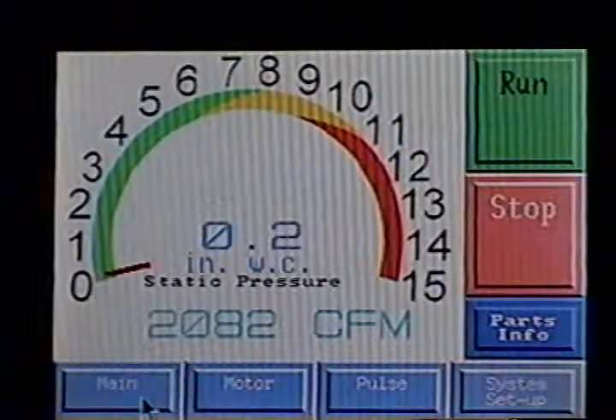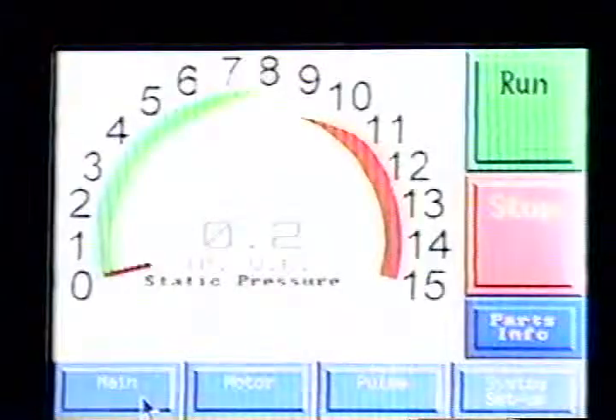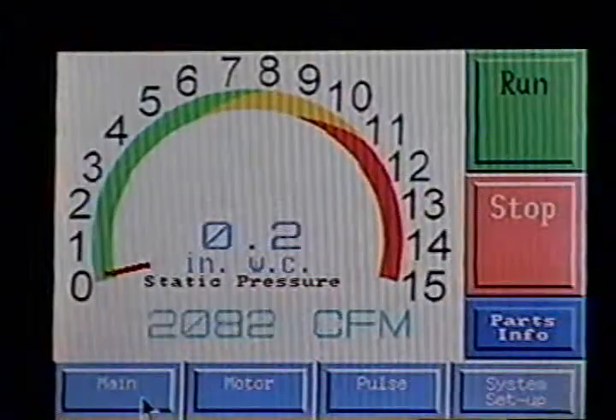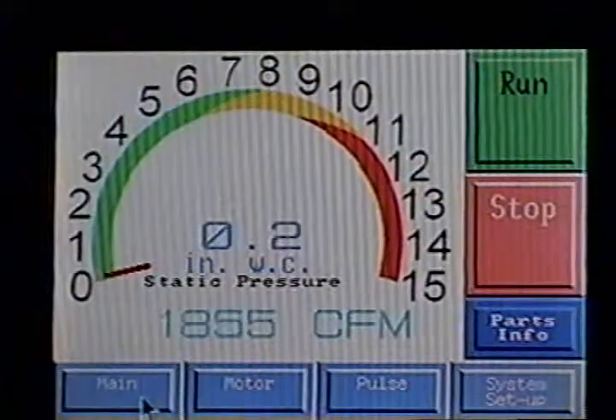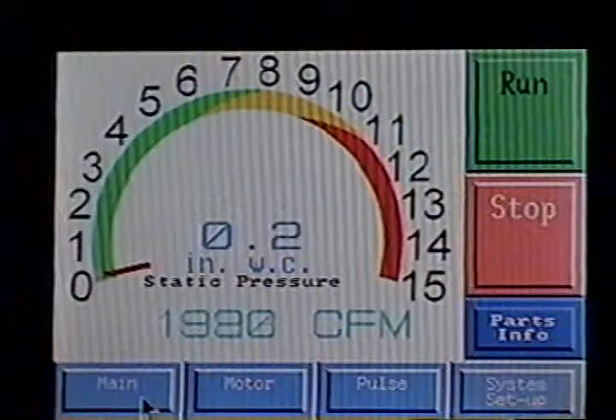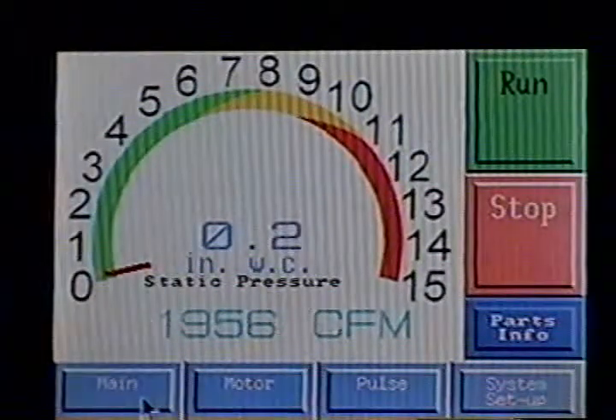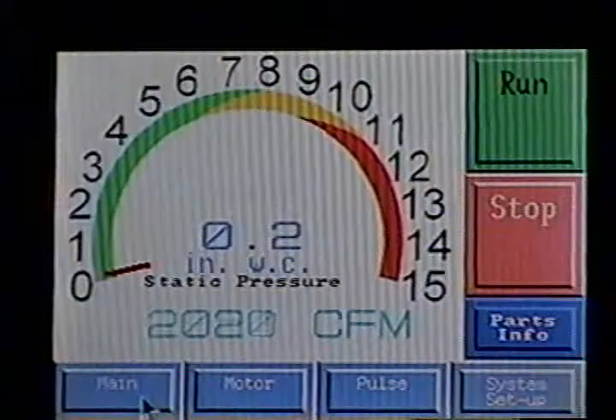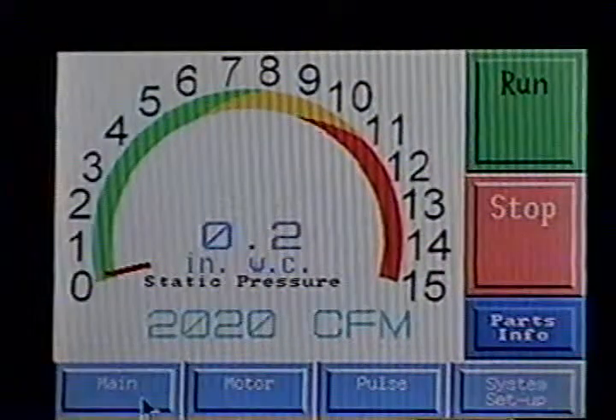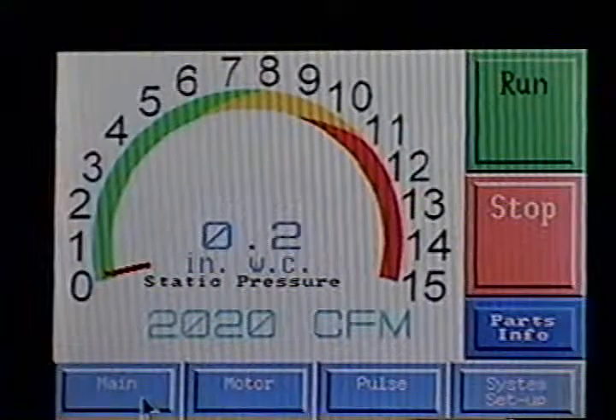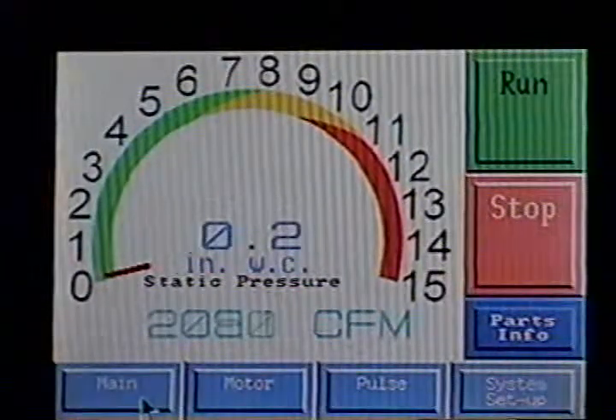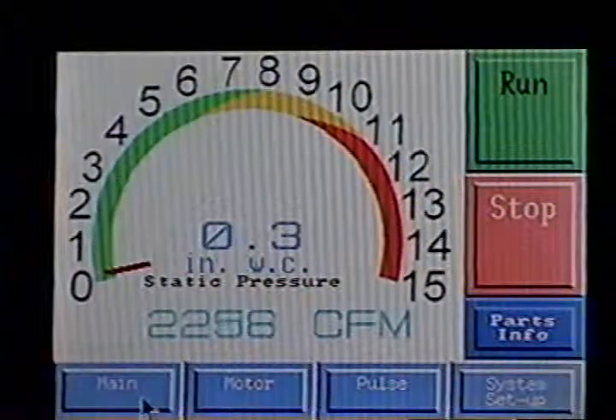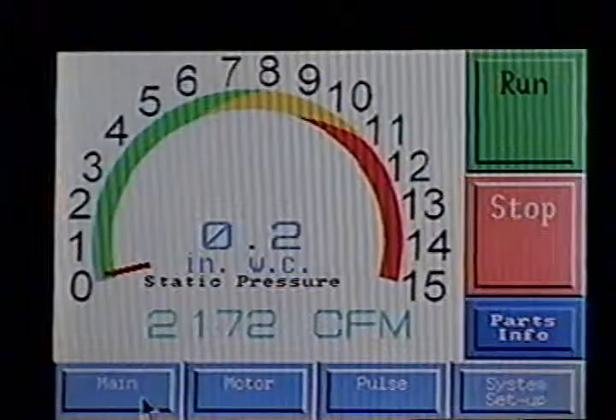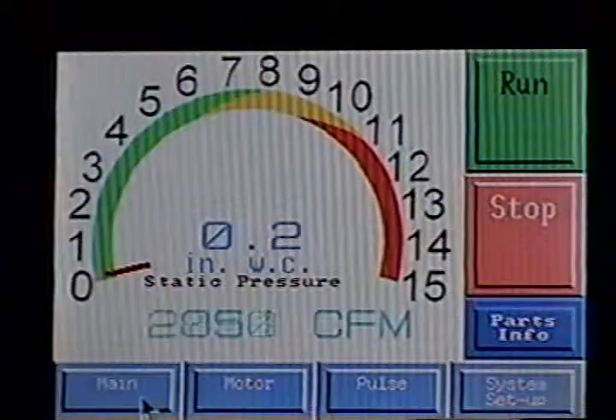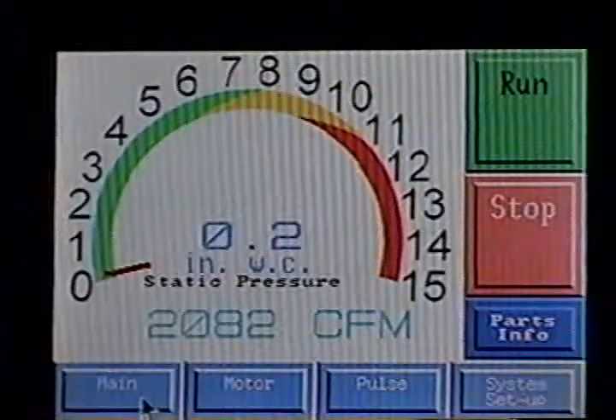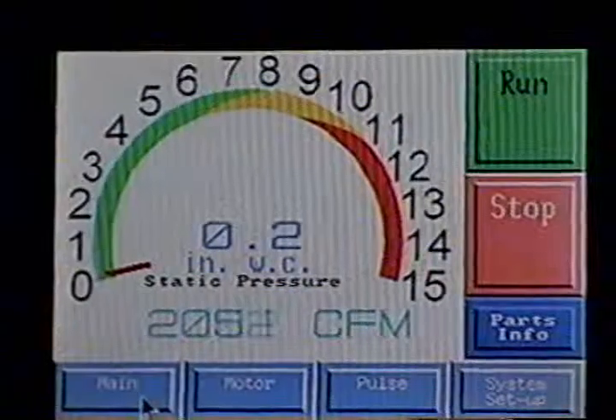Trevor, just take that cardboard and cover up that lower. Either one, I don't care. We're talking about maintaining CFM. Hear the motor change? The motor's speeding up to maintain the CFM. You go ahead and pull that off. The motor adjusts itself, all based on whatever you put in as that value for CFM.